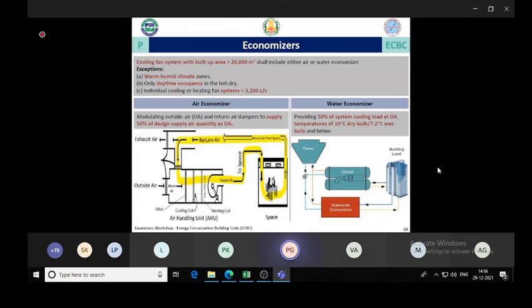Okay, now moving on to the prescriptive requirements. Economizers. So these are required. Economizers are basically devices which can be used to bring in more ambient air, which can be used for free cooling purposes. These are required in certain instances. For example, if the built-up area is more than 20,000 square meter, then economizers are required in certain situations. But it is not required for warm and humid climates. And in case the cooling capacity is less than 3,200 liters per second, in those instances it is not applicable. So for climates like Bangalore, this is required.